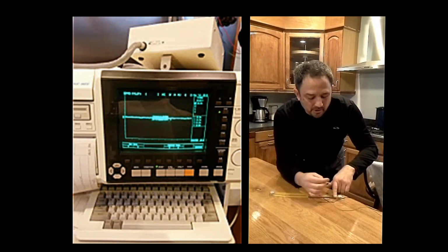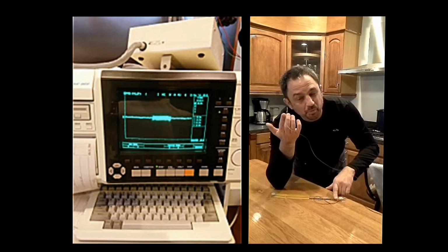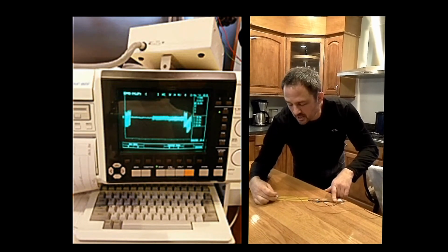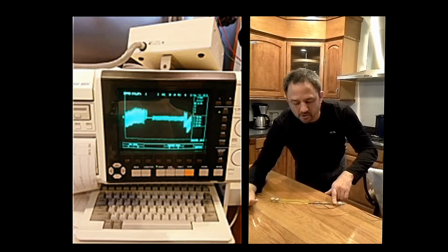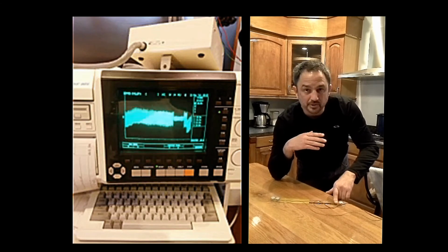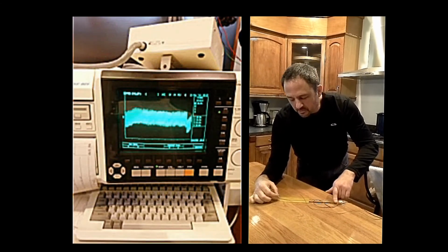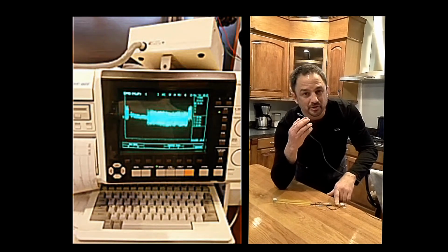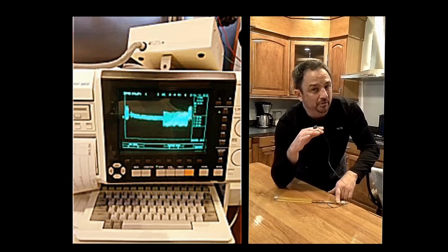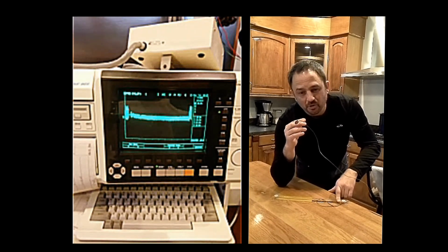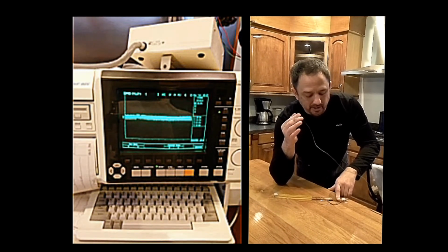And this is important. If I take the isoground and put it in the wrong place, such as where the noise source is not, or near the other recording electrode, I actually amplify the noise, as you can see. So it's very important for us to understand what this isoground position does. It can be wonderful in decreasing noise. It can also be bad in amplifying noise.